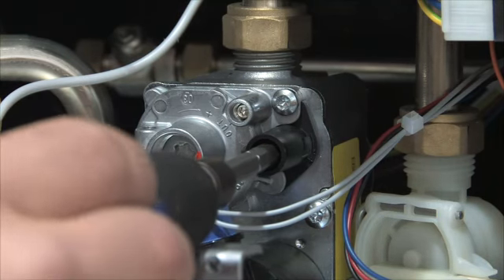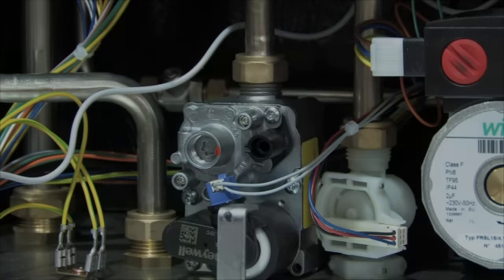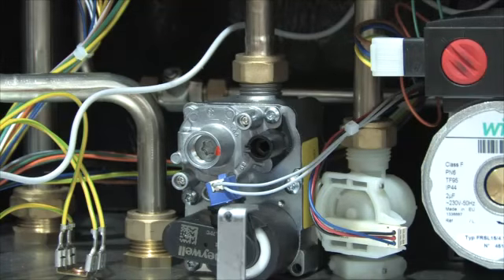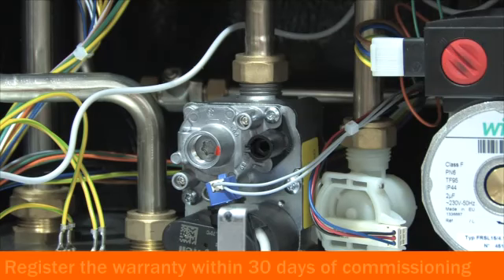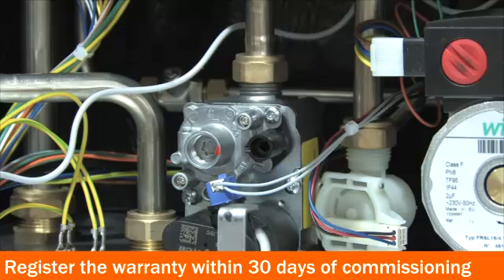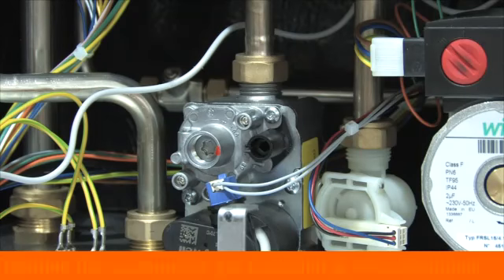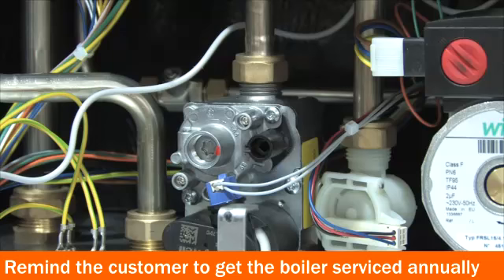Adjust the throttle with a 4mm hex key, turning clockwise to increase. Once the correct readings are obtained, reduce to minimum and recheck. Remove the probe and replace the cap on the flue and gas valve. Don't forget to register the boiler's warranty within 30 days of commissioning the appliance, and make sure you remind the customer that they must have the boiler serviced annually as part of the warranty terms and conditions.